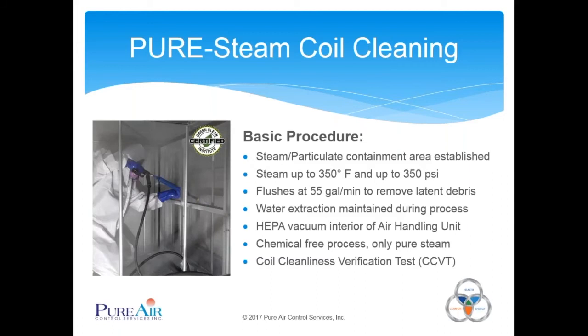So the basic takeaway is... Yeah, I want to mention something too here, Troy. Even though you mentioned it's similar to a pressure washer, it's not actually a pressure washer. This is not Big Joe's pressure washing shop here. In fact, no one should actually be pressure washing their coils, it could damage your coils. This is a high volume, low pressure process, 350 psi is low pressure, and a proprietary process that was developed over the last 33 years here at Pure Air, doing this type of work, and also having done almost 600 million square feet of building so far.